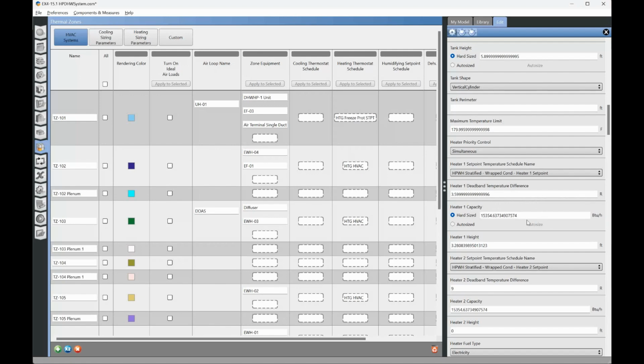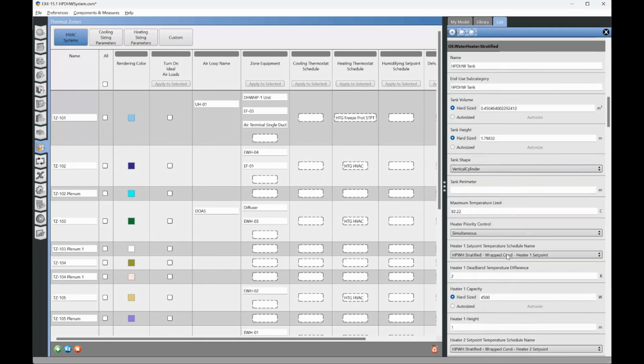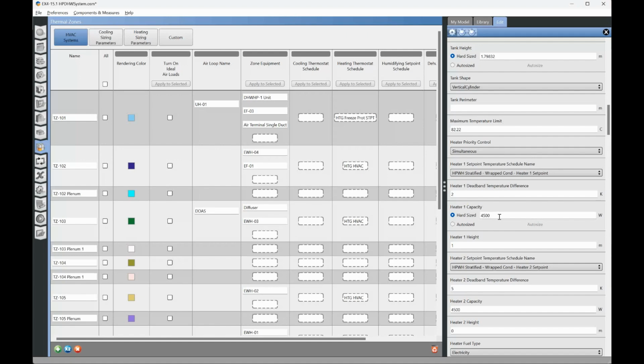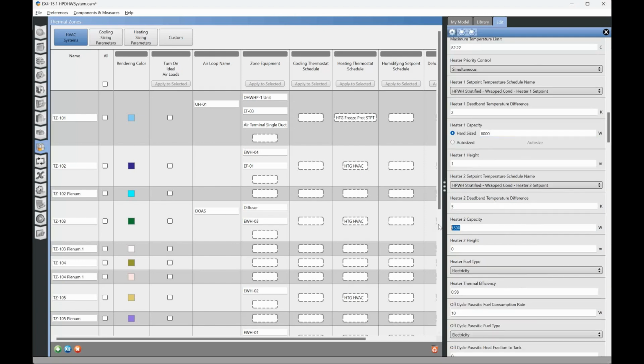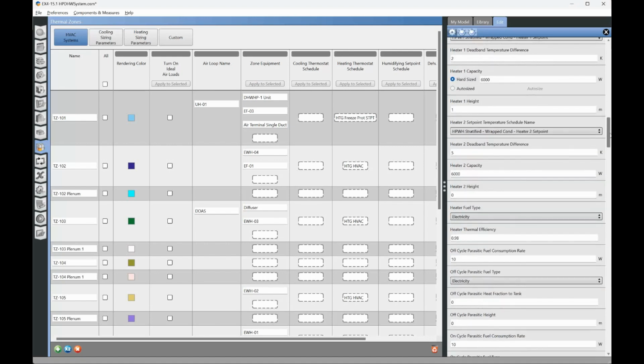So since the capacity for the heaters is in watts, let's switch back to metric units. Let's see. Heater 1 capacity for this was going to be 6,000 watts, and the heater 2 capacity is going to be 6,000 watts. So that'll give us a total of 12,000 watts, 12 kilowatts. As we discussed, the heater set points are 120. It looks like heater 2 has a 5-degree dead band, so the heater 2 would kick on at 115. So it's fine.